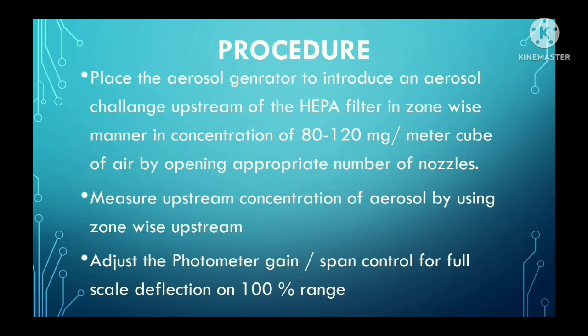Now we will see the procedure for filter integrity test. Step 1: Place the aerosol generator to introduce an aerosol challenge upstream of the HEPA filter in a zone-wise manner at a concentration of 80 to 120 mg per cubic meter of air by opening the appropriate number of nozzles.